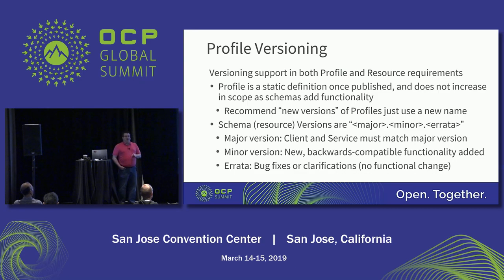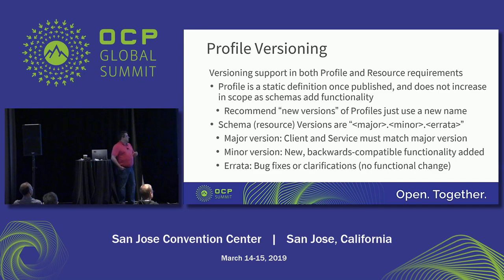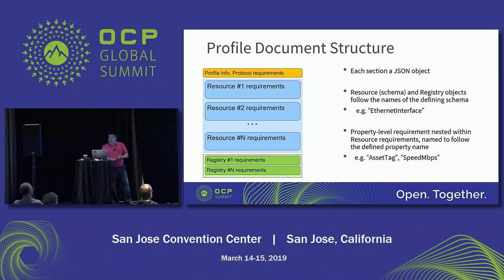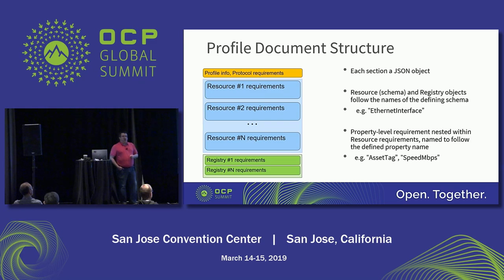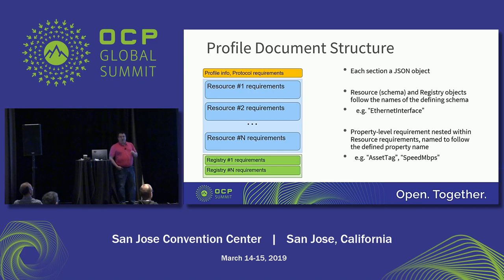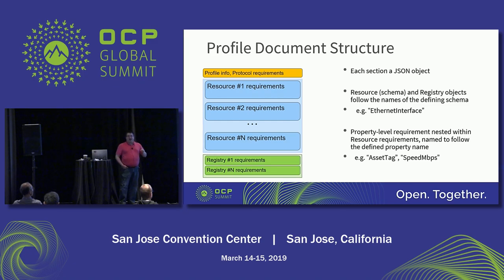Major indicates a non-compatible change — we hope everything sticks at version one and we don't want to break anybody. Minor revisions mean a backward-compatible change, so basically enhancements and additions to individual schemas and resources. Errata are just bug fixes, description clarifications, and that kind of thing. The structure of the document is set up to look like the Redfish resources as you would pull them off the wire and look at them in a browser, making it so a human could go down this list like a checklist. The document is broken up into different sections as embedded JSON objects.